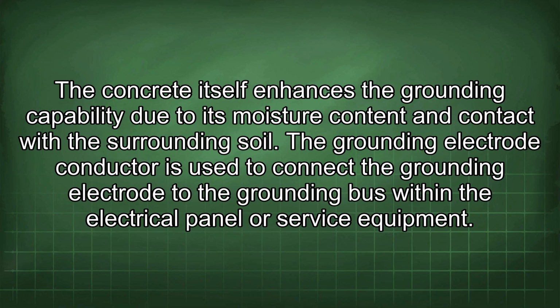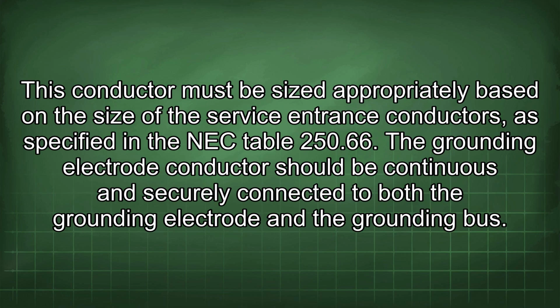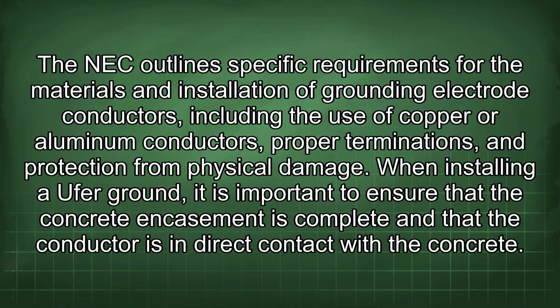The grounding electrode conductor is used to connect the grounding electrode to the grounding bus within the electrical panel or service equipment. This conductor must be sized appropriately based on the size of the service entrance conductors, as specified in the NEC Table 250.66. The grounding electrode conductor should be continuous and securely connected to both the grounding electrode and the grounding bus. The NEC outlines specific requirements for the materials and installation of grounding electrode conductors, including the use of copper or aluminum conductors, proper terminations, and protection from physical damage.